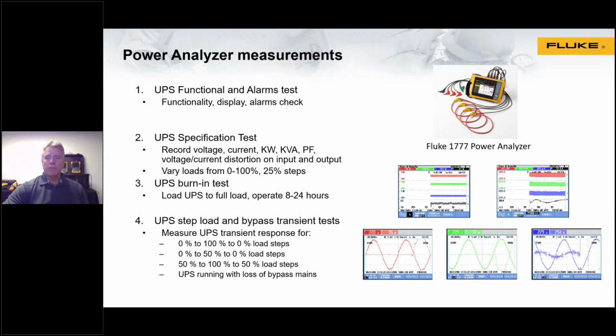So the process for doing this essentially is first using balanced loads. Again, we're using a load bank here. So first you would use balanced loads, run the test, vary the loads from 0 to 100%, 25% steps, and then record the data. And then also using unbalanced loads. There is a process for doing that. So there will be 4 combinations that you would initiate using your load bank.